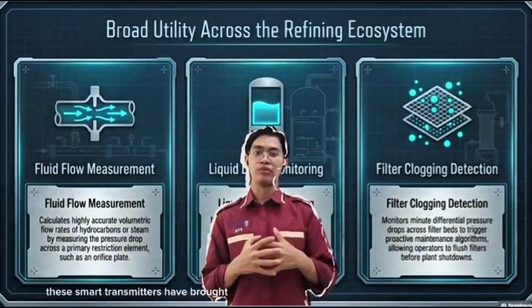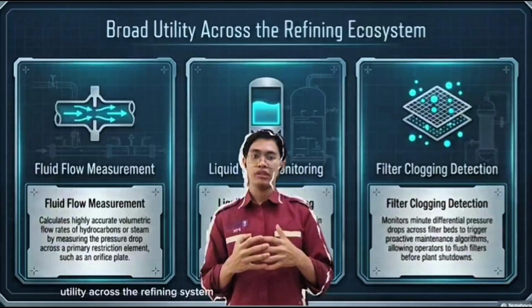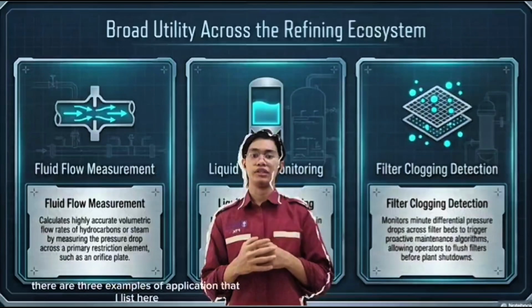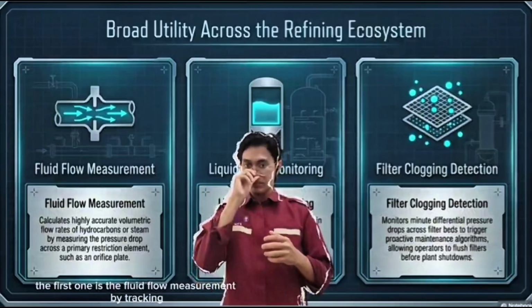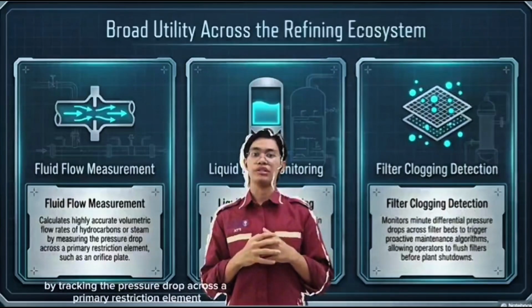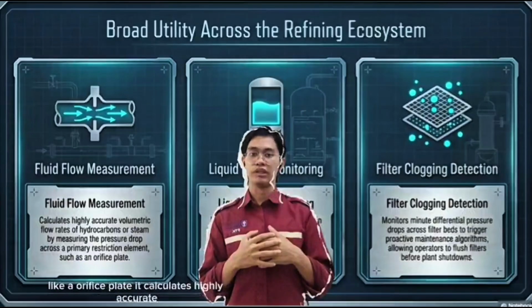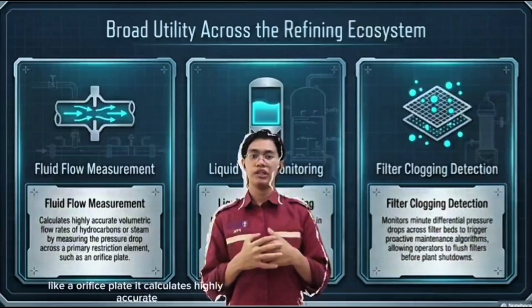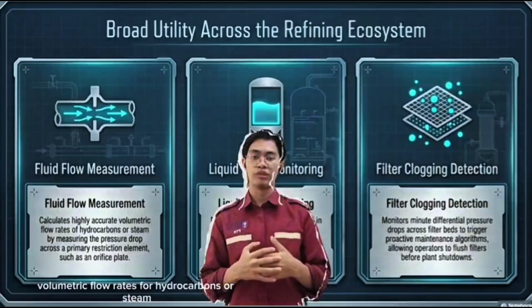These smart transmitters are utilized across the refining system. There are 3 example applications that I list here. The first one is fluid flow measurement. By tracking the pressure drop across a primary sensing element like orifice plates, it calculates highly accurate volumetric flow rates for hydrocarbons or steam.